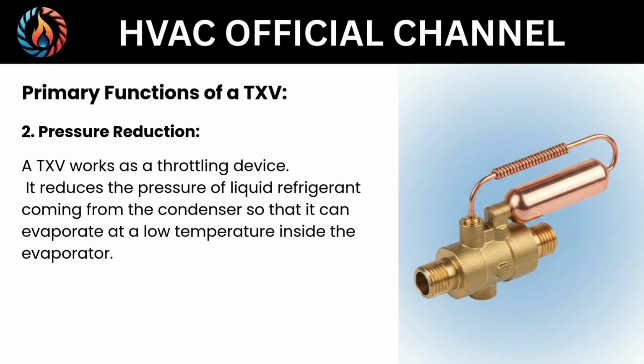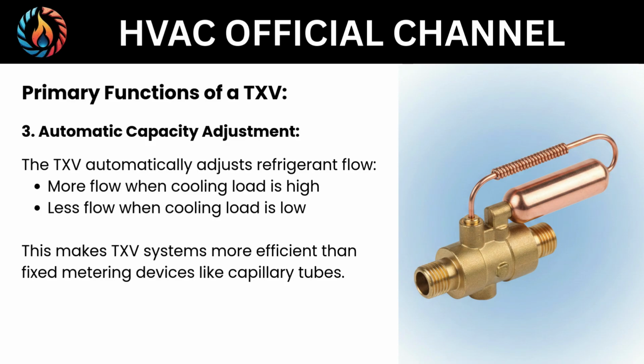2. Pressure reduction. A TXV works as a throttling device. It reduces the pressure of liquid refrigerant coming from the condenser so that it can evaporate at a low temperature inside the evaporator.